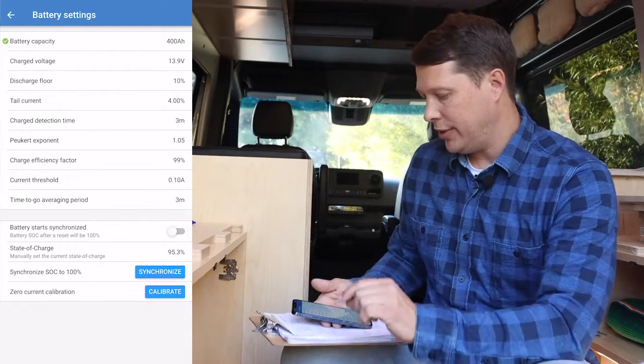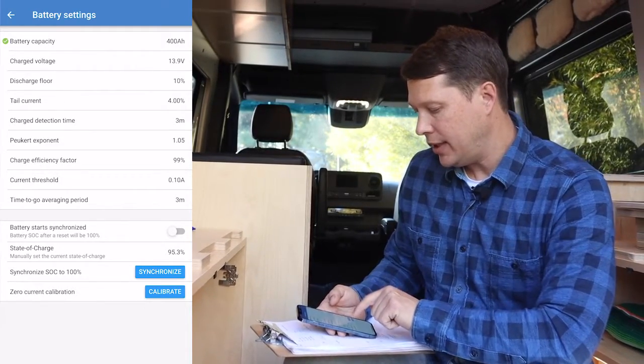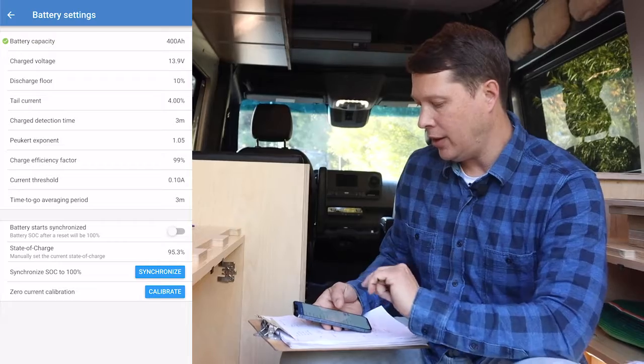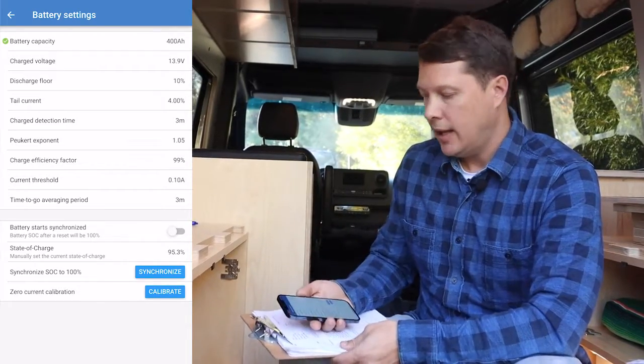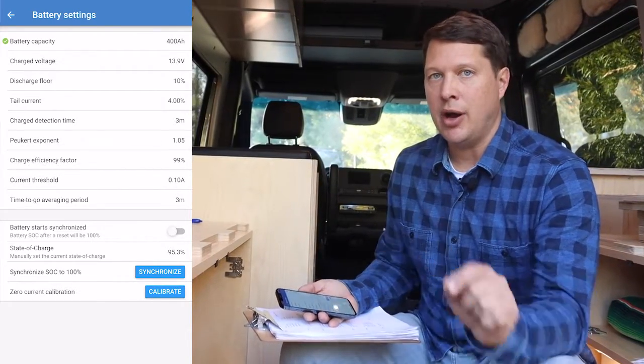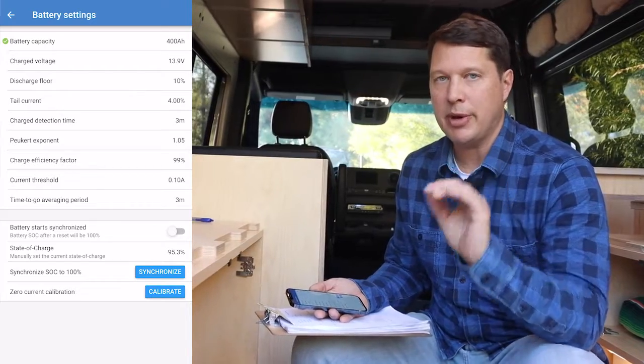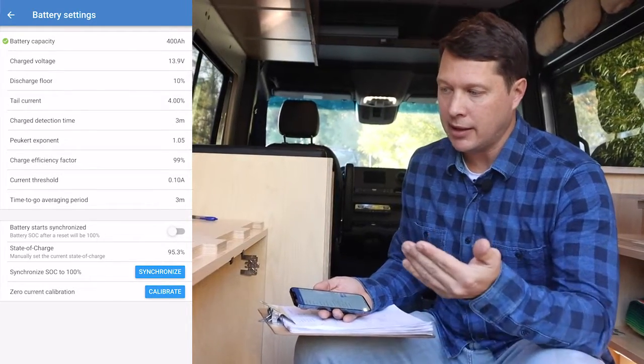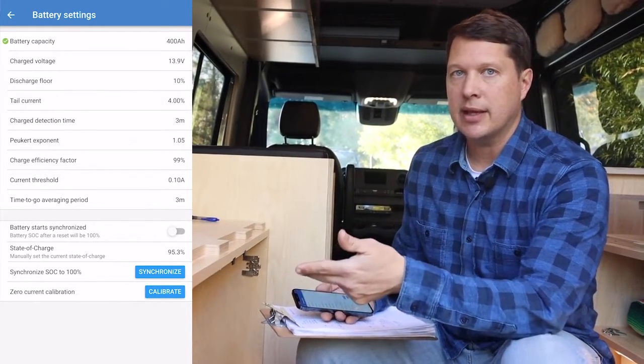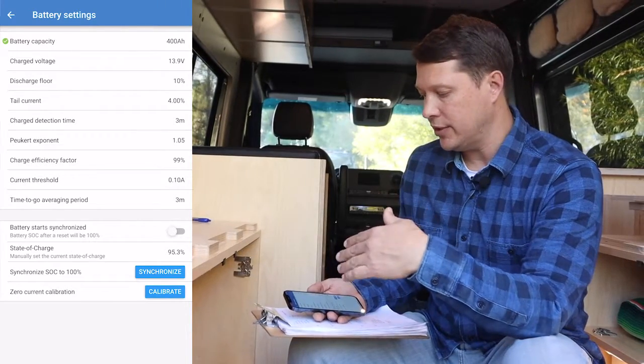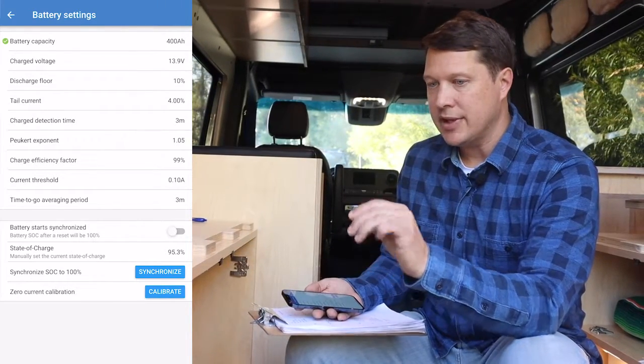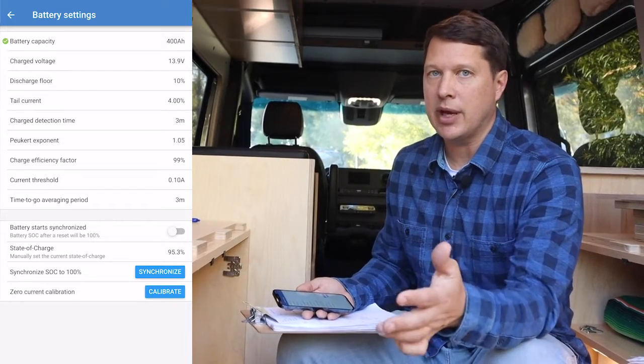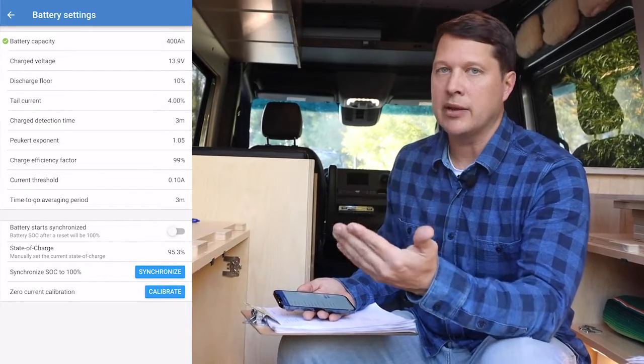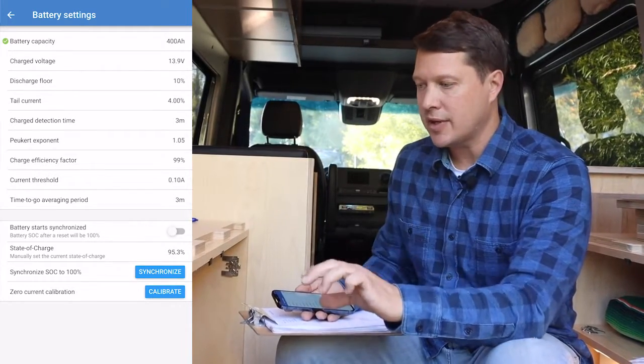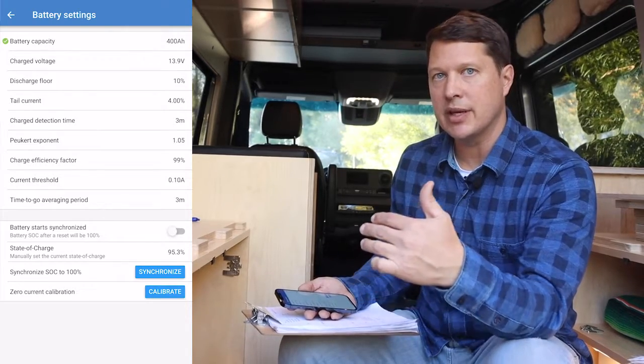Okay, another important setting here: there is a battery starts synchronized on-off switch in the settings, and that should definitely be turned off, because otherwise every time you power down your batteries and you turn them back on, the shunt is going to think that they are at 100%, which you definitely don't want, because it is common to shut down your battery system when you're not using it. Ideally, when it comes back online, you want to have at least some indication of where the battery percentage had left off.